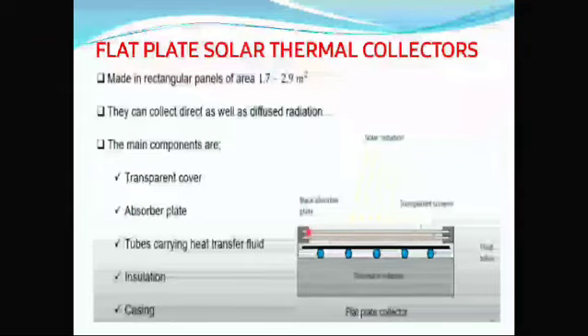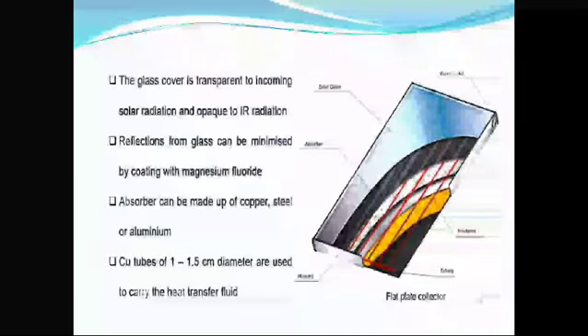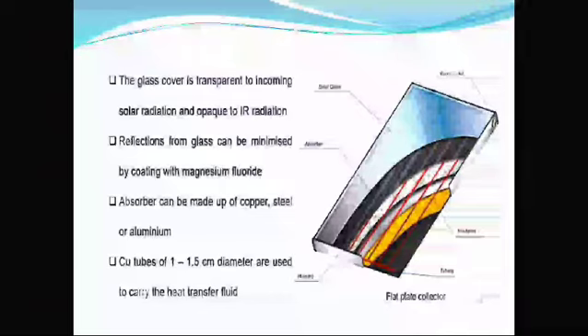The flat plate solar thermal collector is made in rectangular panels. They collect both direct and diffused radiation. The main components are a transparent cover, absorber plate, tubes carrying heat transfer fluid, insulation and casing. The glass cover is transparent to incoming solar radiation and opaque to IR radiation. Reflections from glass can be minimized by coating with magnesium fluoride.